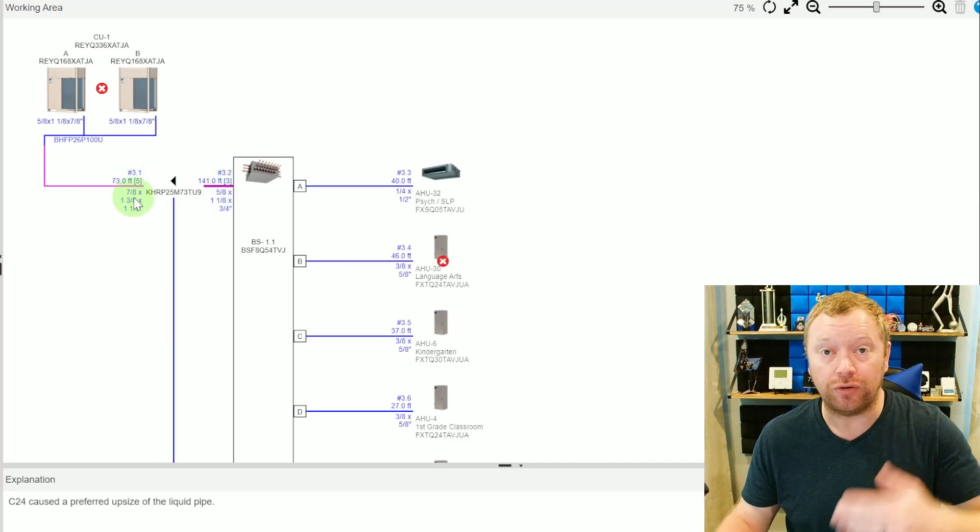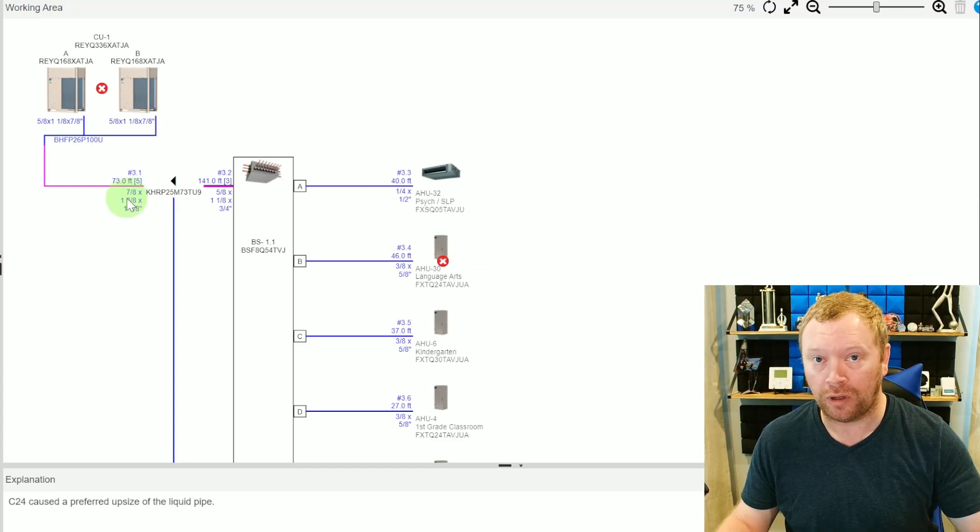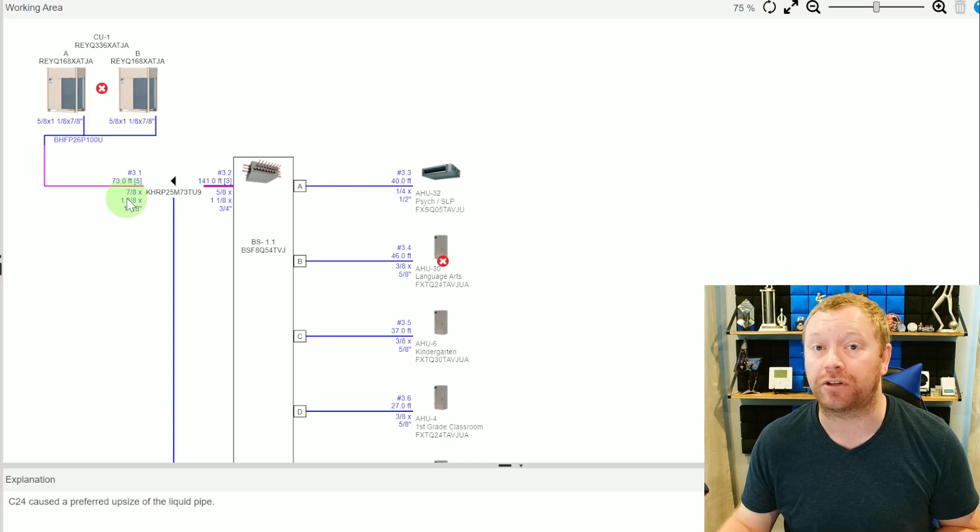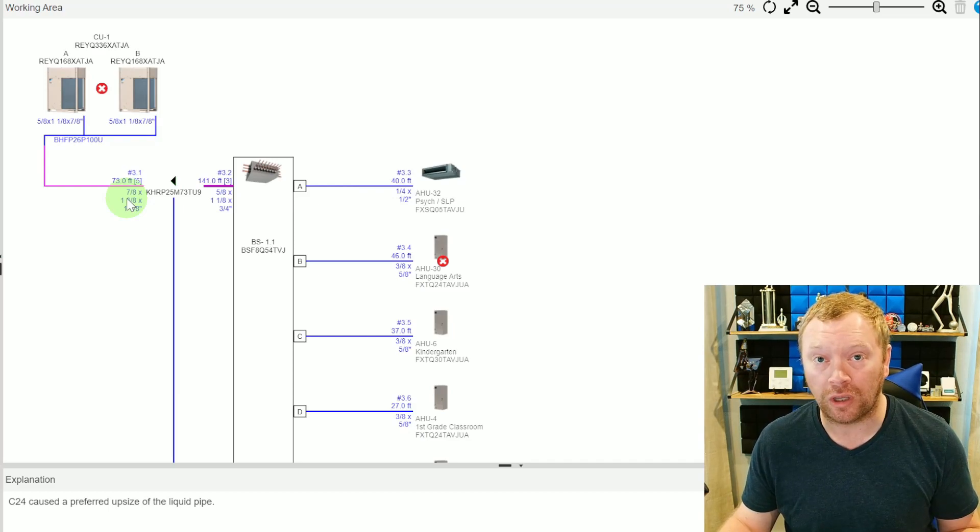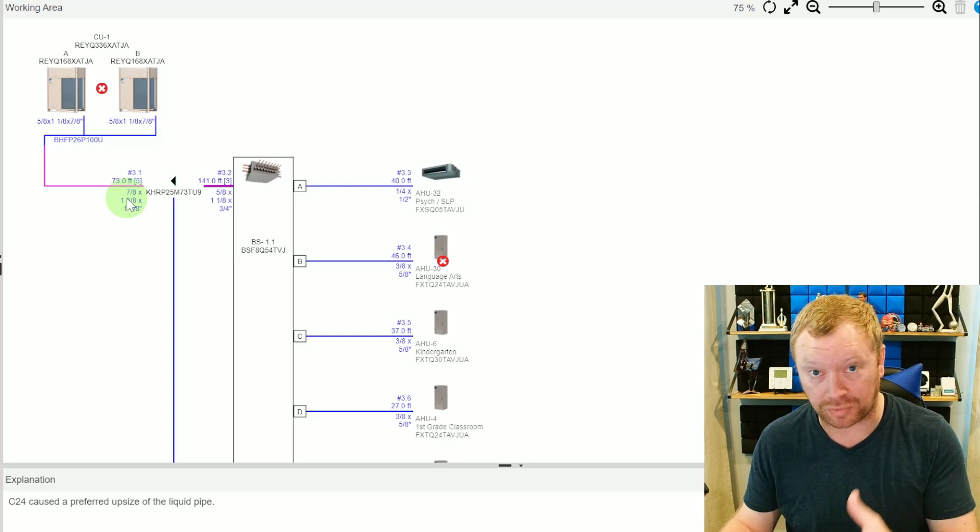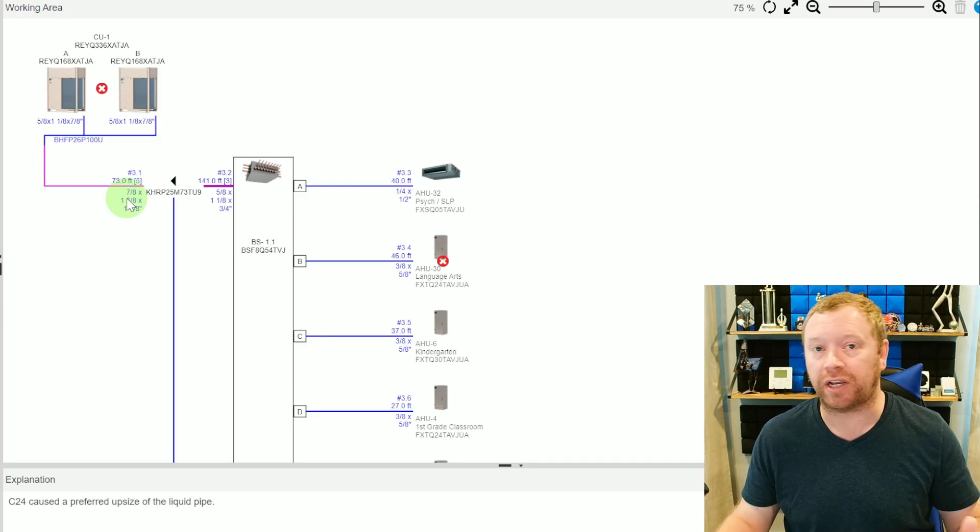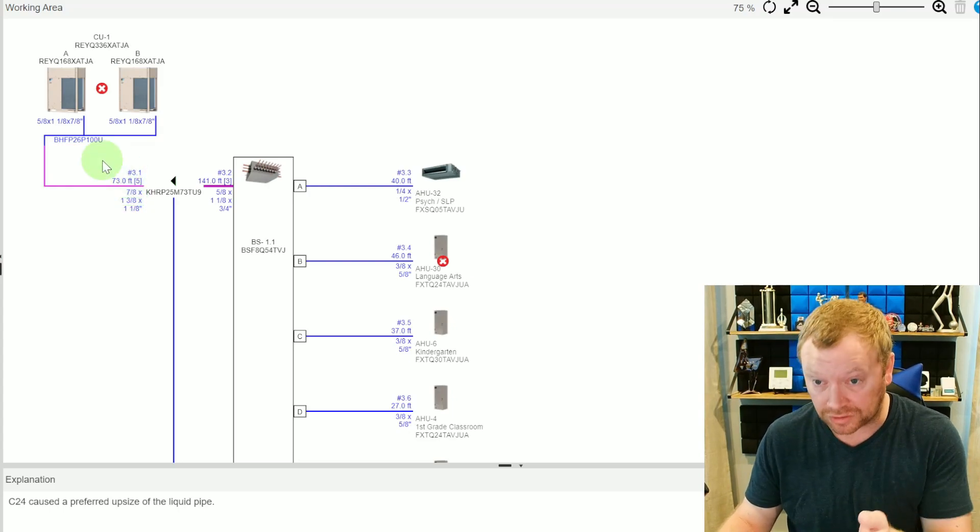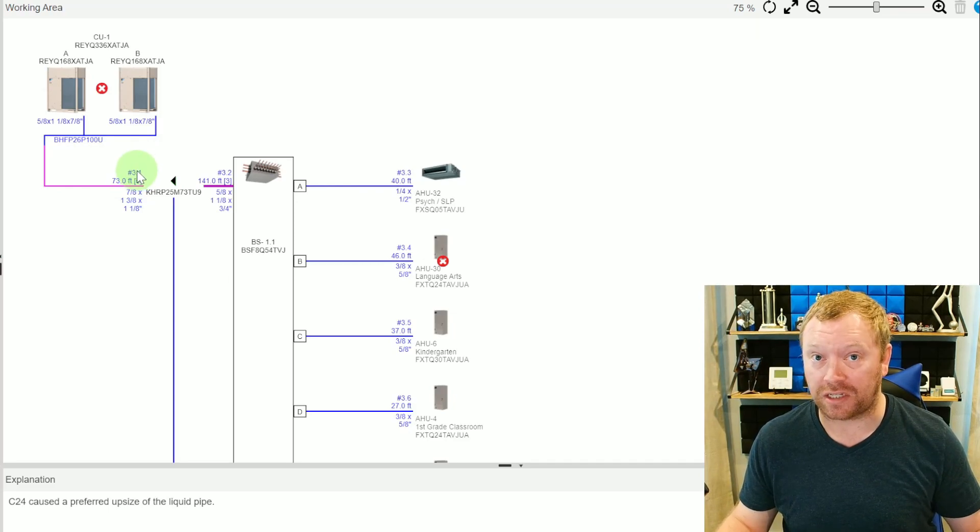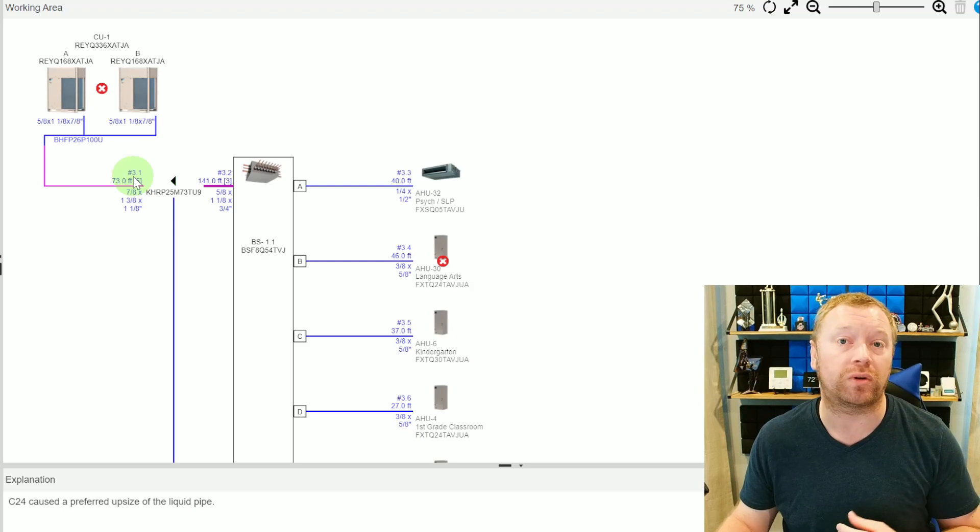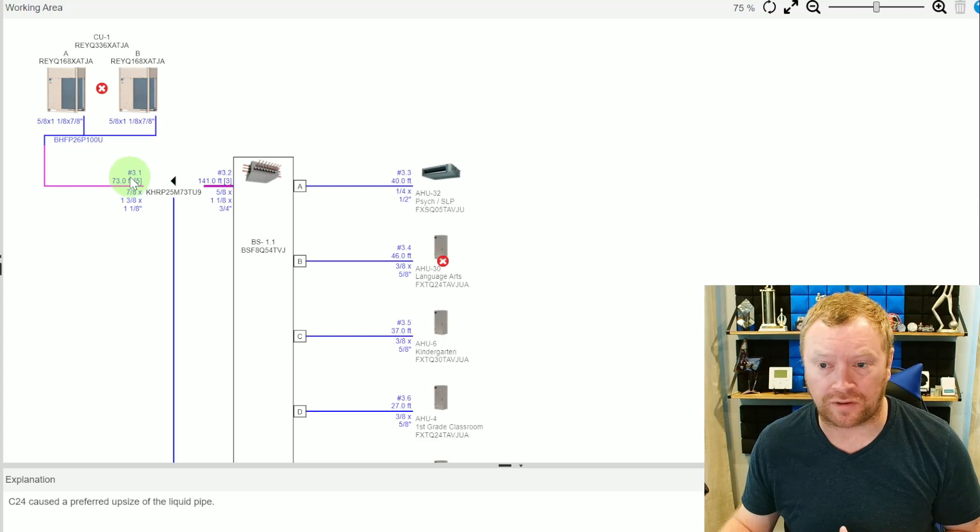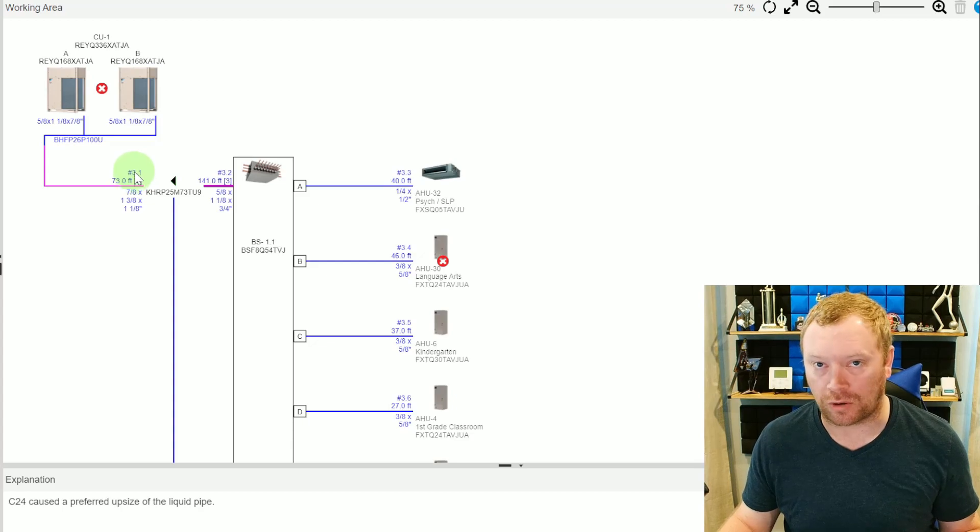We'll talk about that maybe a little bit later or in another video. That's not really the point of today's video. The point of today's video is you notice now we have a pipe size change here and a pipe size change here. If you don't do your due diligence by walking through the job site to make sure that the pipe lengths that are predetermined based on the initial takeoff of the job are going to work, and you just install everything that shows on the initial set of plans without double-checking things, without double-checking and triple-checking to make sure we're not breaking any rules, then when it comes time and you're on pressure test, or you've pulled a vacuum and you want to know what's the refrigerant charge, and you send all these numbers back to your vendor, or you plug them into the software to get a charge, you're going to notice that, oh crap, I have to go back, and now I need to change out copper.